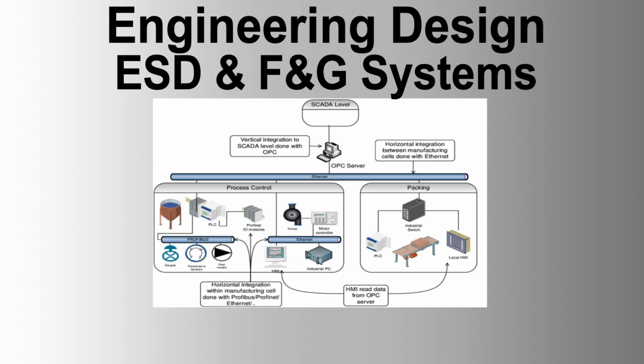2. Notification and interface. All alarms and actions initiated by the ESD F&G shall be notified to the DCS and the main control room. The system shall interface with the DCS through dual redundant serial links for status and alarm monitoring. 3. System independence. The F&G system must operate independently of the ESD system to ensure that a failure in one does not affect the other. Separate I/O, hardware, and software must be provided for ESD and F&G functions.